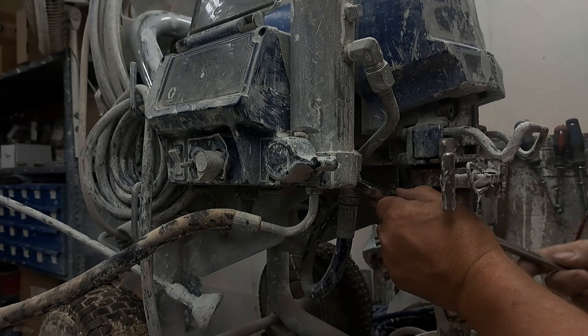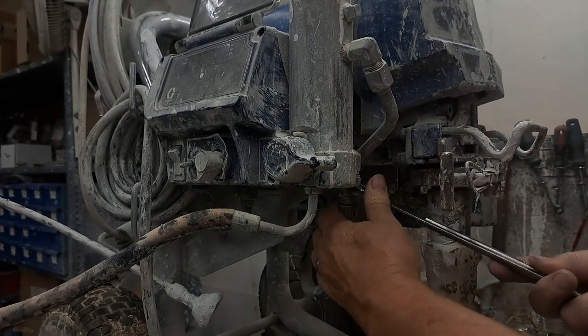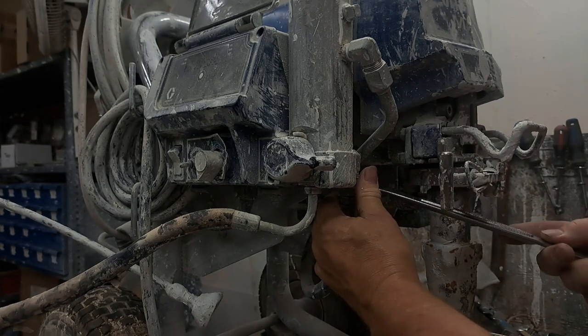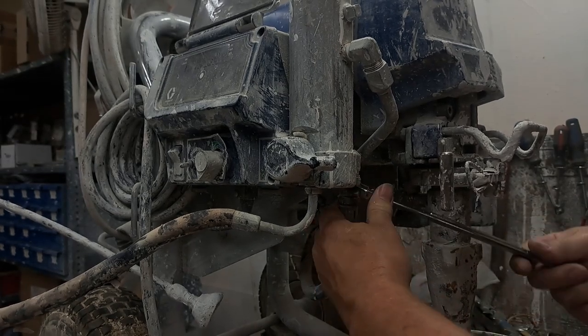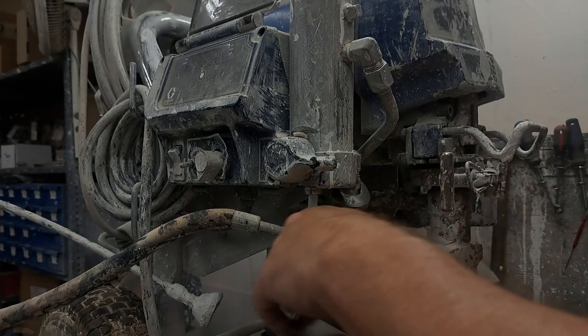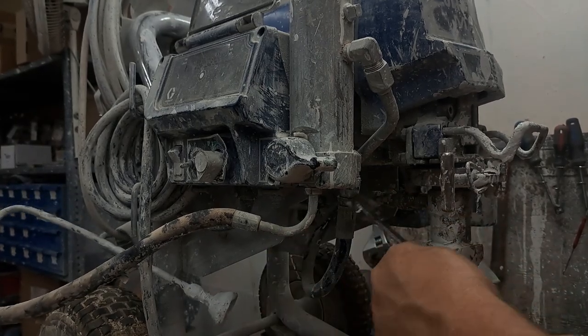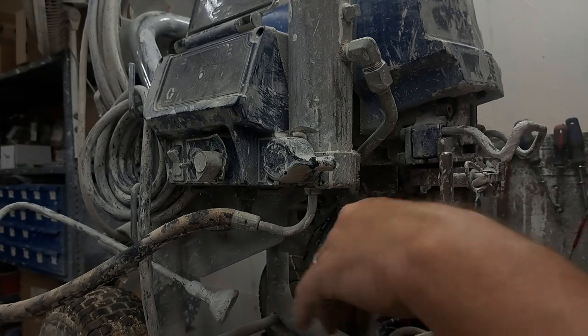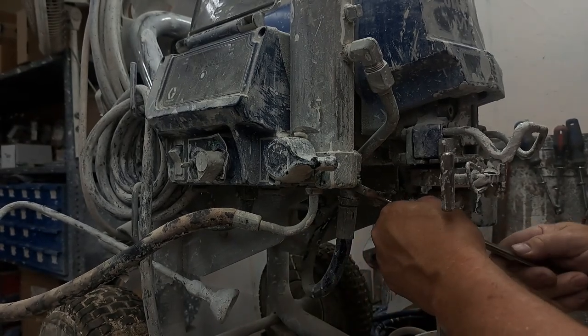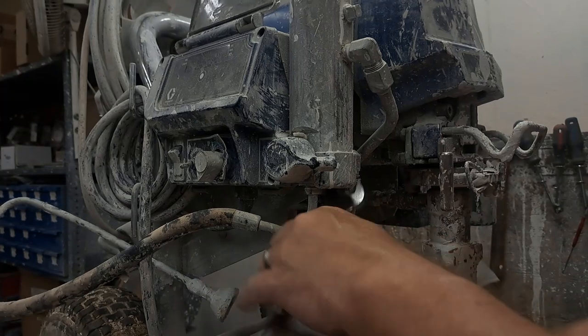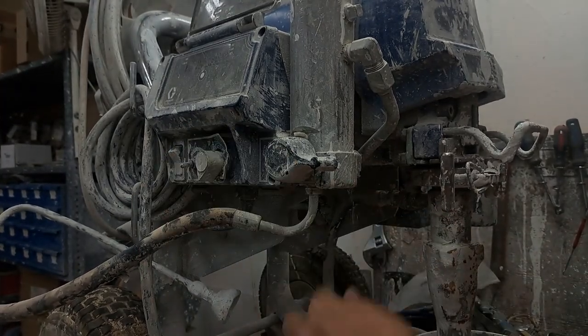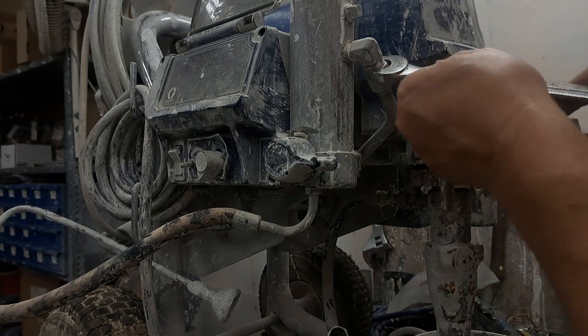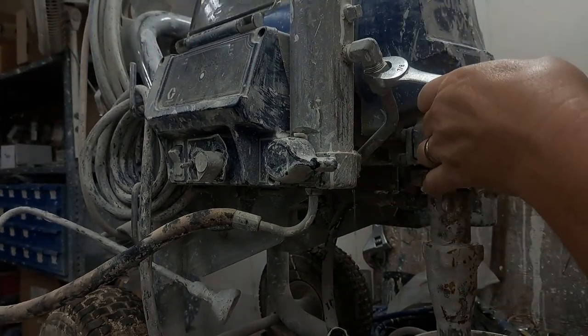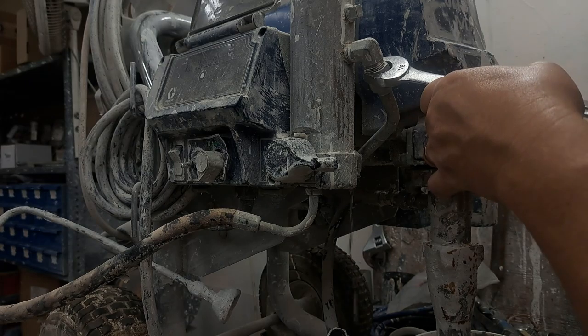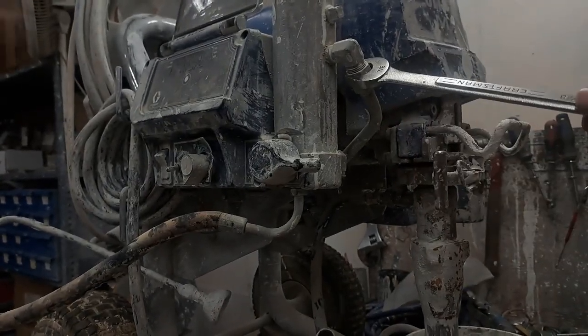Like I say, the transducer can just go bad because it is an electronic part, so eventually it'll just go bad on you. But if it freezes, it's definitely going to be an issue. What the transducer does, as you've probably seen in some of my other videos, is it actually measures the pressure that you set by your pressure control knob over here on the side. So now that's off. We're going to take this off. This is a hard line going to the actual pivot reel on the back of this thing.